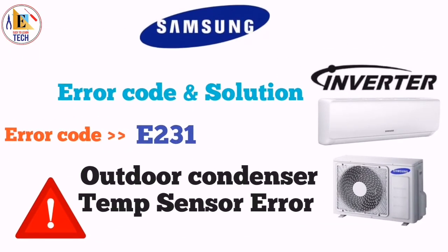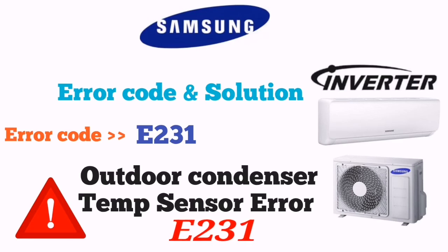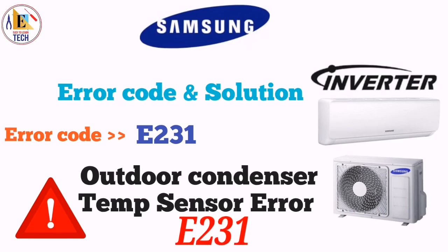When you see error E231 in your outdoor unit, it means outdoor condenser temperature error. At that time, you have to follow the same process as for error E221. Check all the connections, the resistance and the voltage. If the connector is not connected properly, you can follow the process of error E221 and solve the issue of E231.